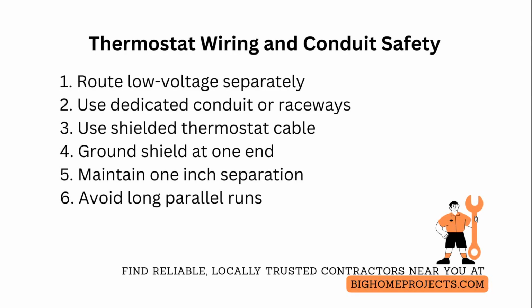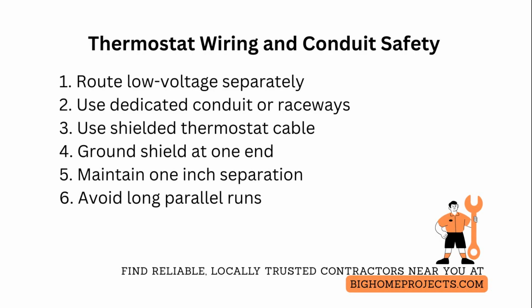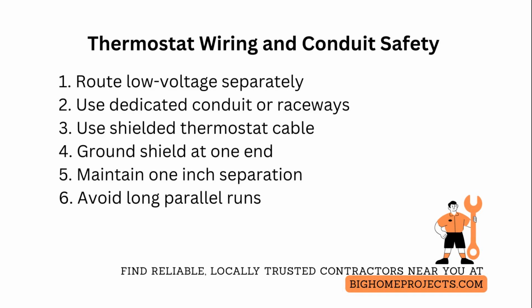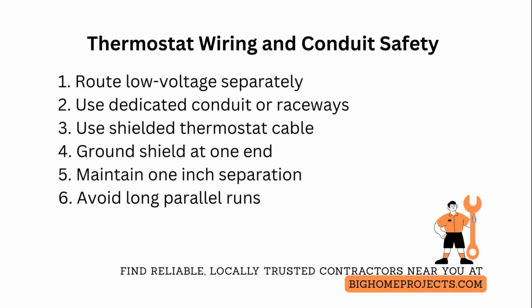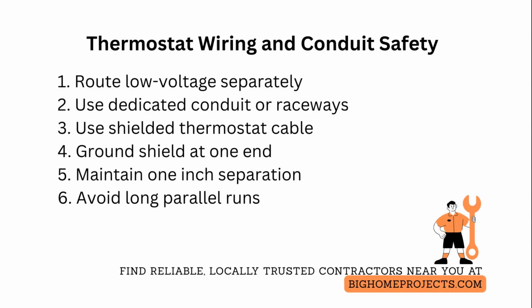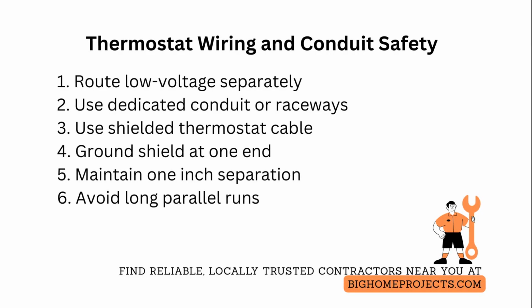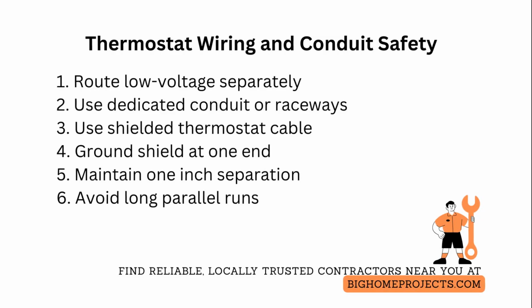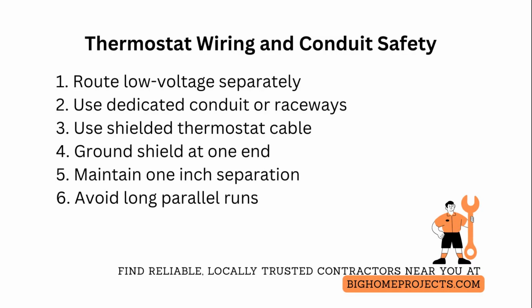When pulling through walls, run low voltage in its own sleeve or inner conduit, and identify both ends with durable labels to speed future troubleshooting. Use a 5 or 6 wire thermostat cable with a common conductor sized per the control device's spec, and verify that transformer secondary circuits are isolated from line voltage by at least the manufacturer's required insulation. Document any shared pathways in your project drawings, and get an inspector to sign off before energizing.